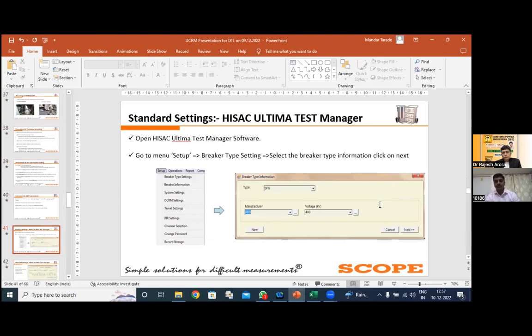First, on your screen it is visible that you need to feed in the breaker information, and if you press yes, you need to set the linkage ratio of your CB. Also, you need to feed in the value with reference to which the default velocity is calculated. According to the thumb rule or industrial rule, or the data received from different manufacturers, they take the reference of the timing: the first touch point and 10 milliseconds prior to the first touch, calculate the slope between these two points and show the default velocity.